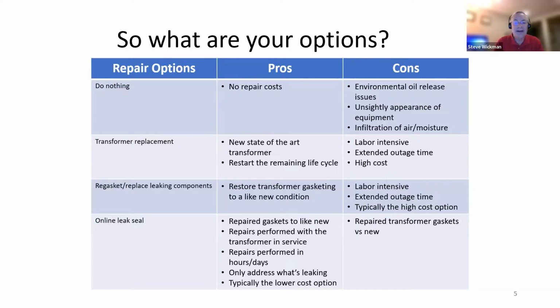And lastly, we talk about online leak sealing, which is what we're going to highlight in the presentation today. The advantage here is you can have gaskets repaired to like-new condition. Many repairs can be performed with the transformer in service. The duration of these repairs is usually measured in hours or days. And in reality, maybe you only address the ones that are leaking at the time, and have multiple visits by a leak sealing outfit to address them as they occur, as opposed to taking the entire transformer out and doing everything all at one time.